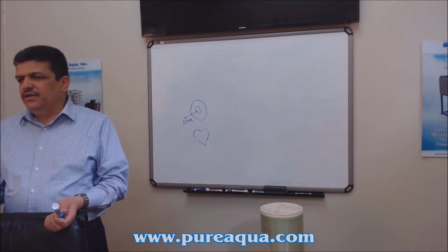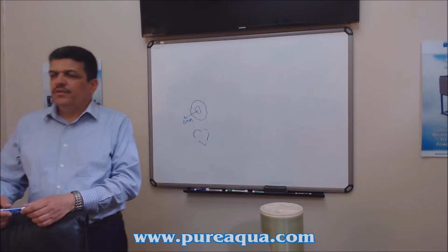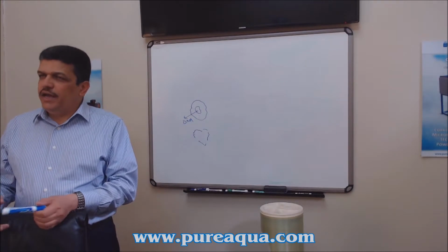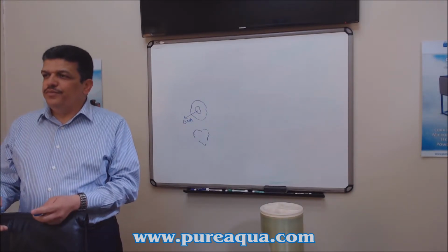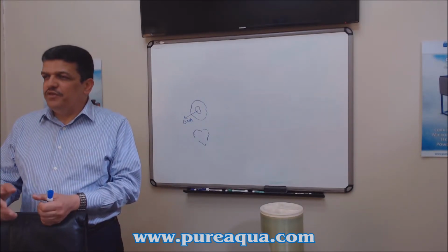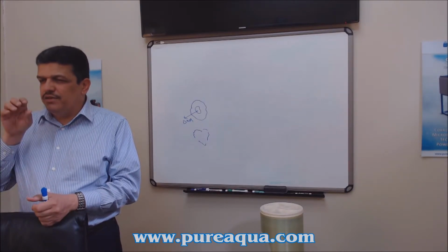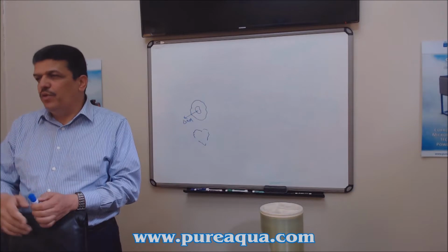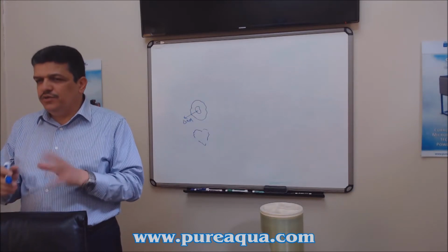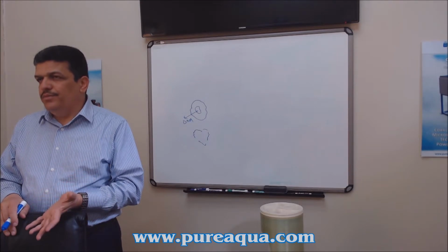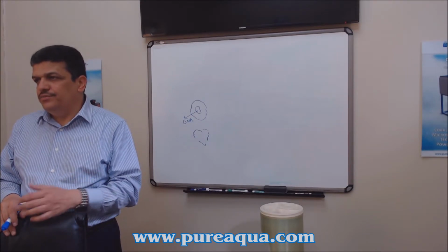That's why in regular applications for water, we always recommend a 5 micron filtration, because you don't want the UV to sterilize water where there is no transmission, where you can't pass the light through the water. So you want to clean it so the water is clear, somewhere like 5 NTU.